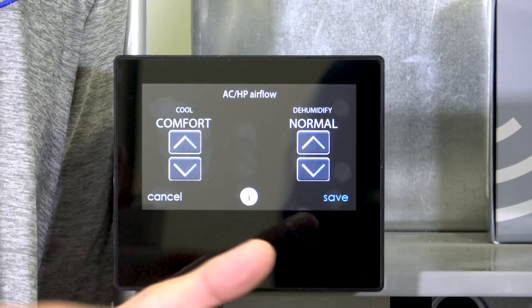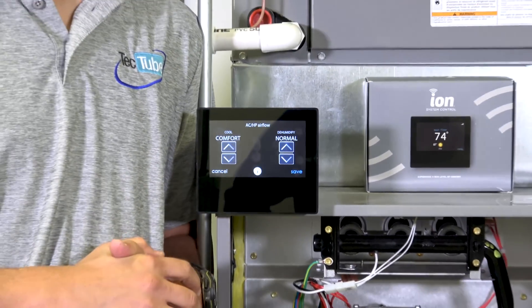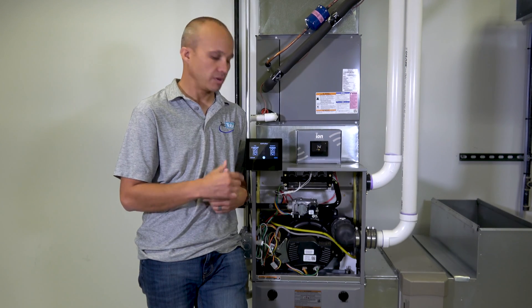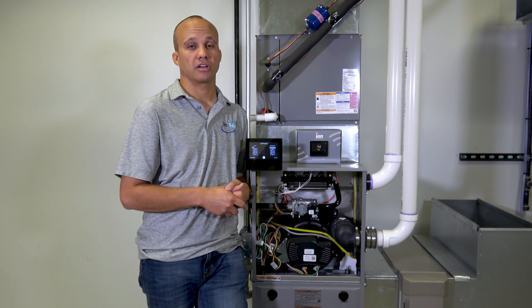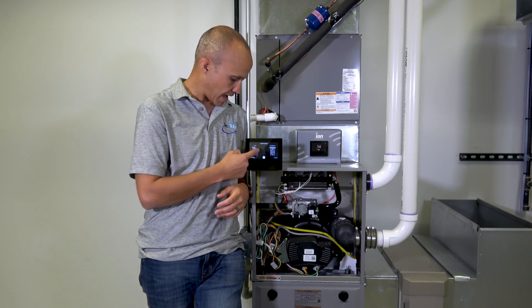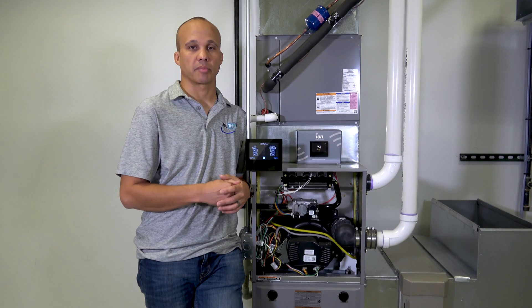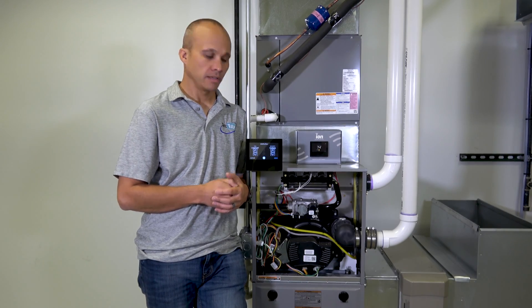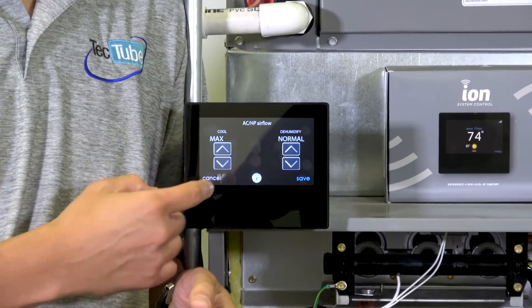Comfort means 300 to 325 CFM per ton — that's the normal scenario, the default, what you want for most projects for good dehumidification control in cooling mode. However, if that's not enough airflow to reach the farthest register, you can go up to Efficiency 325 CFM per ton, or Efficiency 350 CFM per ton. If that's still not enough, Max gives you 400 CFM per ton — the traditional 1960s–70s number. Nowadays we default lower for better moisture control, but you can go up to 400 if needed, knowing it'll be louder and won't dehumidify as well.